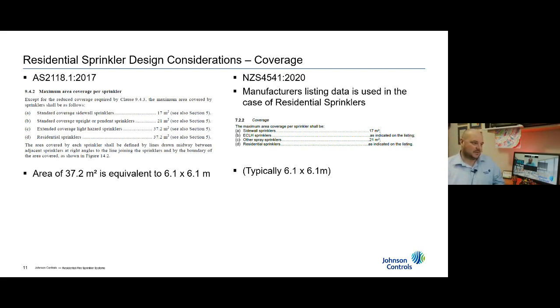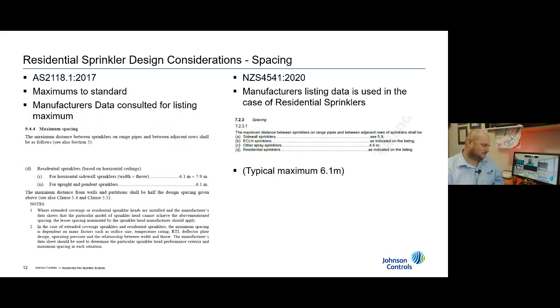17 square meters for a sidewall, 21 square meters for standard coverage upright or pendant sprinklers, and where we do differ is that the Australian standard gives us a number which is 37.2 square meters for both extended coverage light hazard and residential sprinklers, which is based on the manufacturer's information of 6.1 by 6.1 meters. In New Zealand, they do it slightly differently, so there is a reference to the manufacturer's listing, which is typically 6.1 by 6.1. So it says the same thing in a different way.